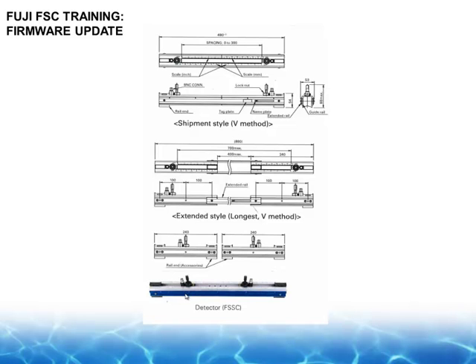This blue bar is also a slide that you can take and slide to the left and to the right, so you can do a V configuration up to 24 inches without disassembling the transducers. So it slides into, it transforms is a better word, into a larger transducer, rail-wise. And if you'd like to do a Z configuration, guess what? They pop off and you have two separate rails, each containing a transducer or sensor head. So this is way cool for your small applications and your large applications. So it's adaptable to go from 2 inches to 40 inches and probably a little larger than that.